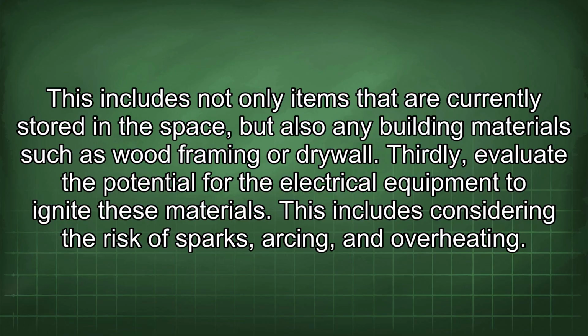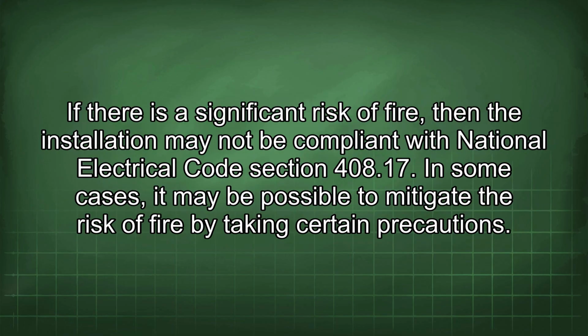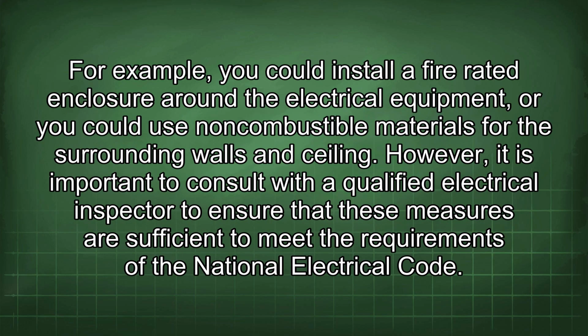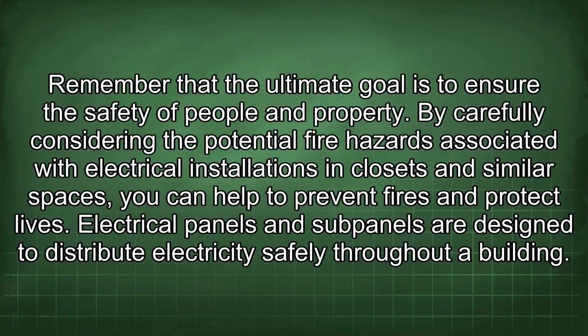This includes considering the risk of sparks, arcing, and overheating. If there is a significant risk of fire, then the installation may not be compliant with National Electrical Code Section 408.17. In some cases, it may be possible to mitigate the risk of fire by taking certain precautions. For example, you could install a fire-rated enclosure around the electrical equipment, or you could use non-combustible materials for the surrounding walls and ceiling. However, it is important to consult with a qualified electrical inspector to ensure that these measures are sufficient to meet the requirements of the National Electrical Code. Remember that the ultimate goal is to ensure the safety of people and property. By carefully considering the potential fire hazards associated with electrical installations in closets and similar spaces, you can help to prevent fires and protect lives.